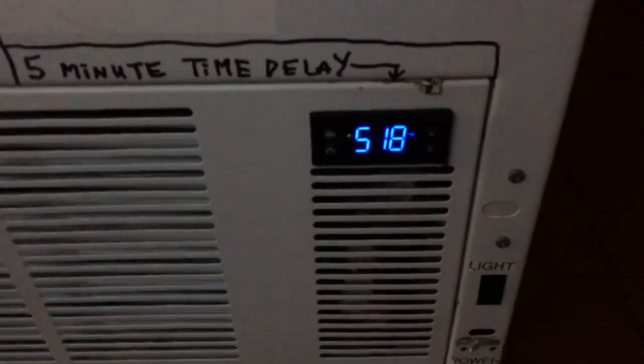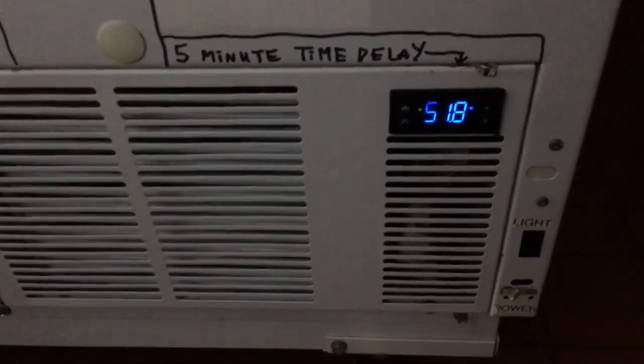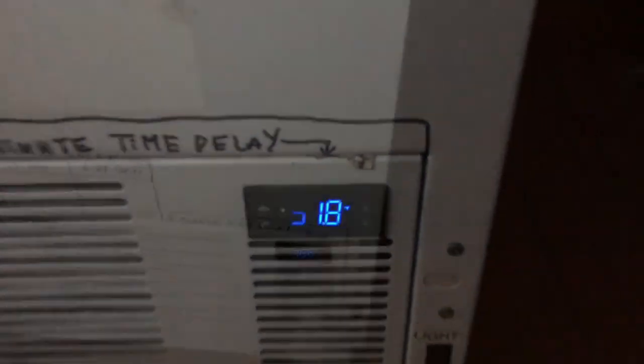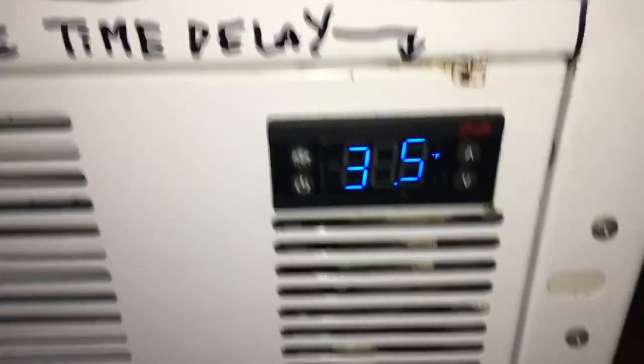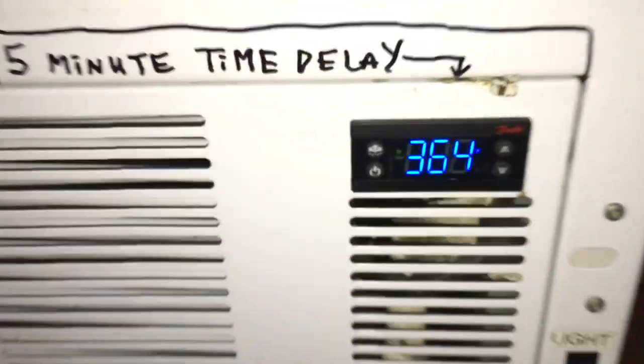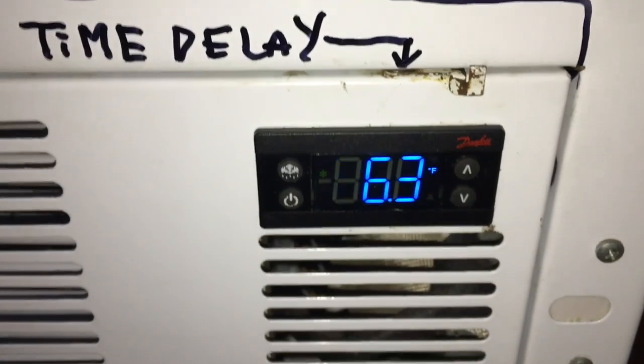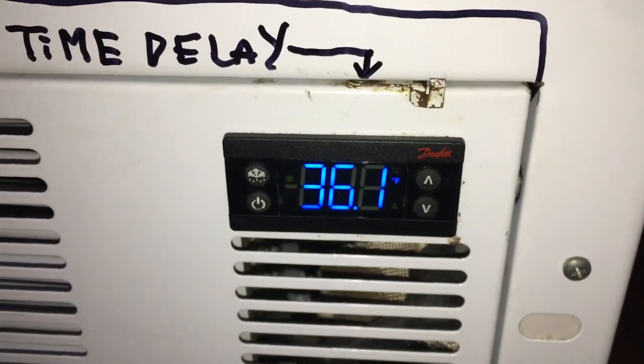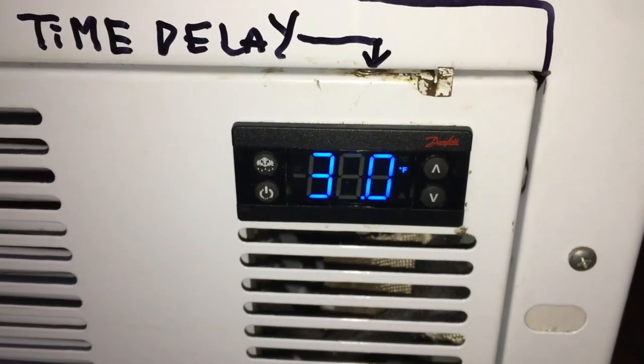It's working a lot better now - a lot happier with it. It's been running just 5 minutes and it's coming down like 5 degrees. Clean condenser makes all the difference, that's for sure. Definitely kicking butt a lot better now - 36.5 degrees. Clean condenser, what a difference!